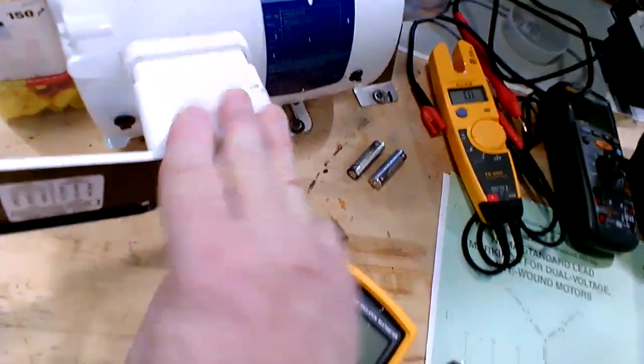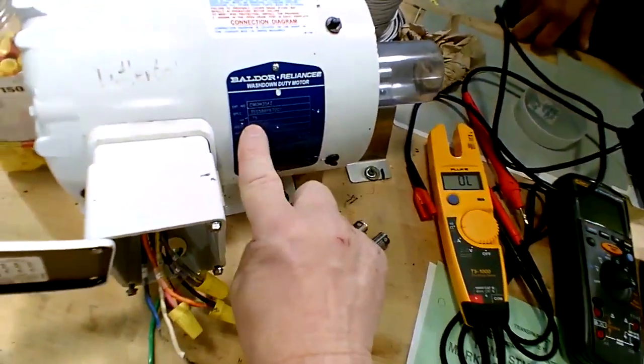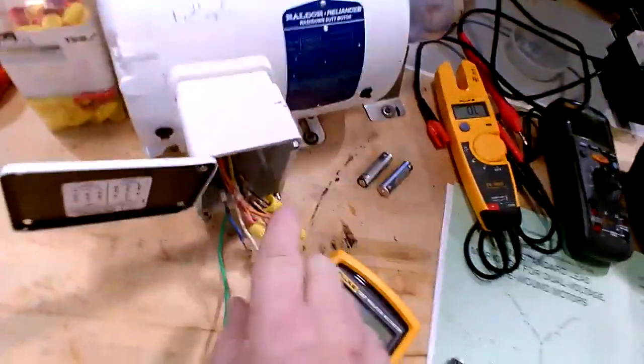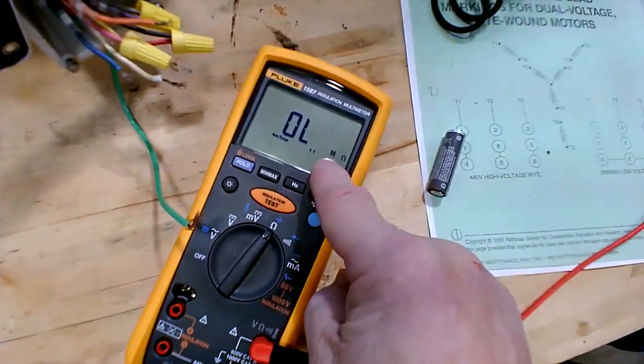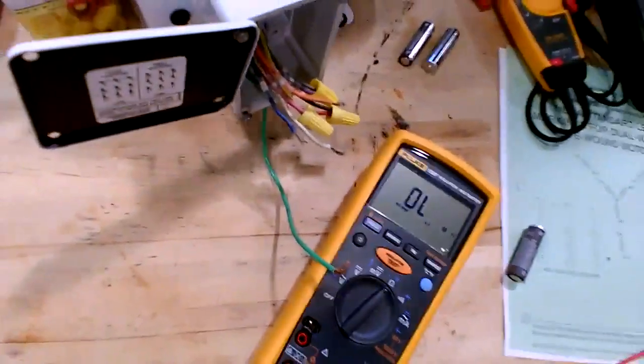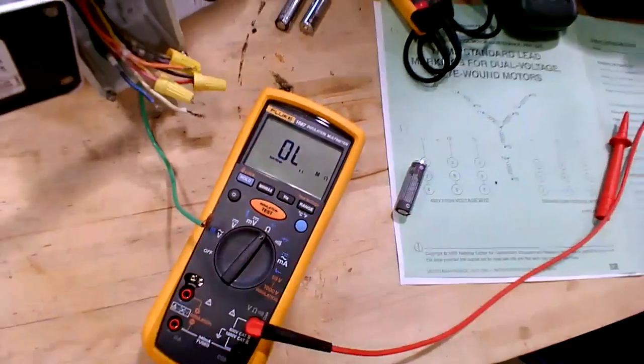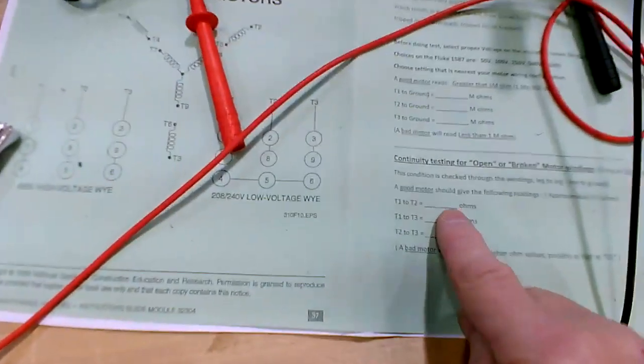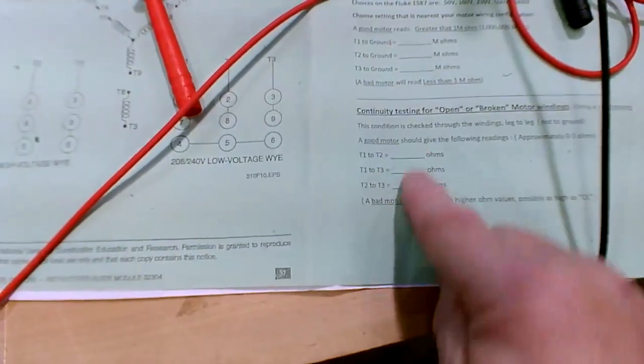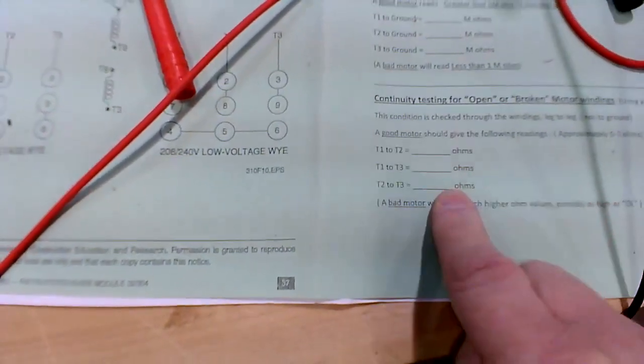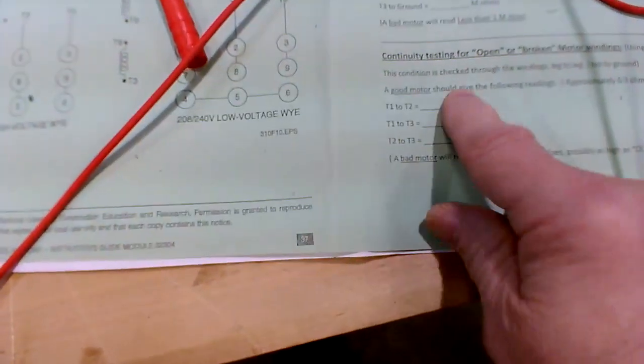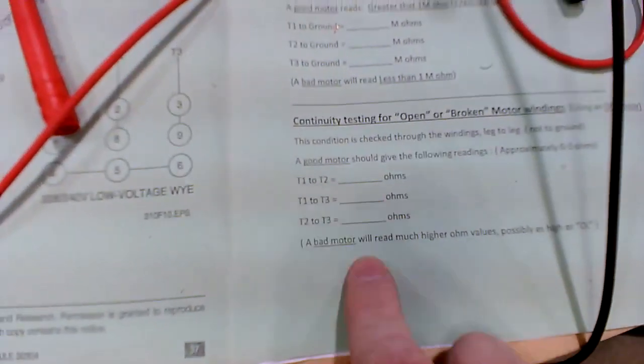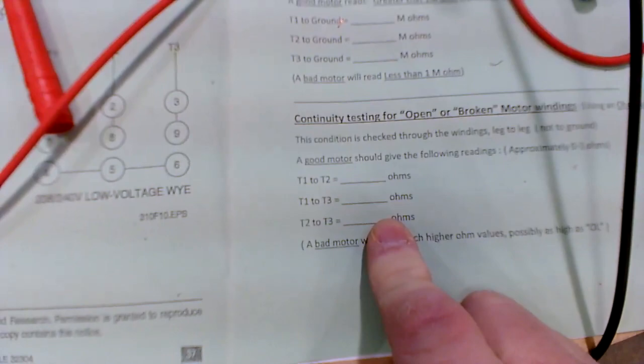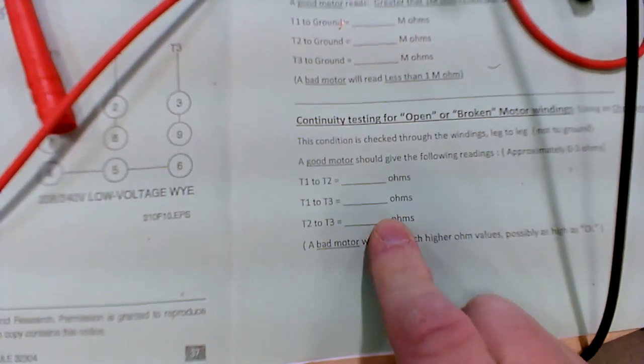When you go to a bigger motor, the larger the motor it is, when you get above this, this is a 3/4 horse. If you go to a 5 or 10 horse, the wires are much bigger and the resistance is much less. So them numbers ain't going to be no 20 ohms. They're just going to be way on down. It might be down around 1 ohm or 2 ohms because the windings are really big and they got very low resistance. So these numbers over here, the 20.3 or whatever it is, you write those numbers in there, and they're supposed to be what you consider to be balanced. They need to be balanced numbers. If the resistance on these is not similar, then there's something wrong with the winding. Okay? Does that make sense?